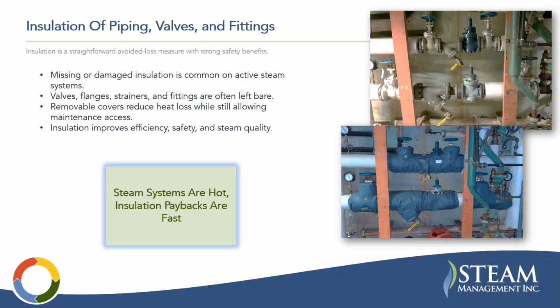So removable covers reduce heat loss while still allowing maintenance access. Insulation improves efficiency, safety, and steam quality. Any energy lost in the steam system is basically going to generate condensate, and that's going to affect your steam quality. When we say steam quality, we mean dryness of steam. So the more water that drops out of the steam, the worse the steam quality is going to be. The more that water is going to pool up in the bottom of pipes and in drip legs and get entrained in the steam as it's traveling through.